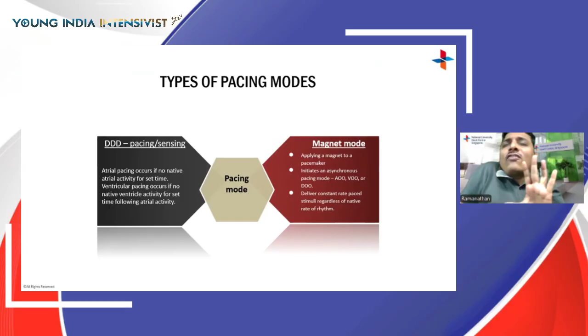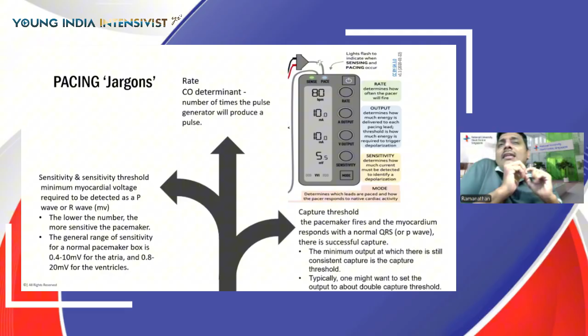Now, we spoke about the modes, we spoke about the various kinds of pacing. There are other pacing jargons that you need to be aware of. If you look at the pacemaker box in front of you, three things will be glaring at you. The first is the rate. That is essentially the number of times the pulse generator would produce a pulse. In short, that is the way you decide your patient's cardiac output. The number of times the pulse is triggered essentially decides the cardiac output, and you usually set the patient's rate anywhere between 70 to 90 in routine practice.